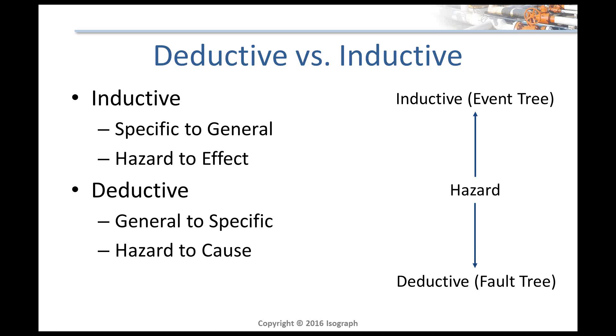You can see how these two are related to each other: both starting from a hazard, fault trees work backwards to figure out the causes, and event trees work forward to figure out the outcomes. These can very easily be linked to each other. You might be using a fault tree to quantify the hazard that serves as the basis for your event tree analysis. Sometimes in this context they're called bow tie events — if you draw the diagrams next to each other it kind of looks like a bow tie.